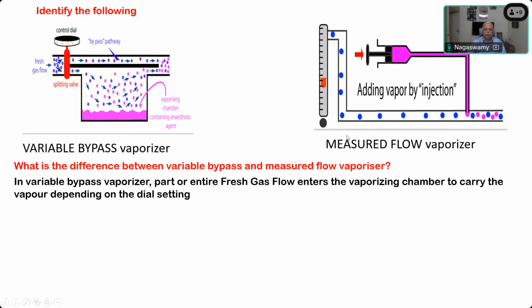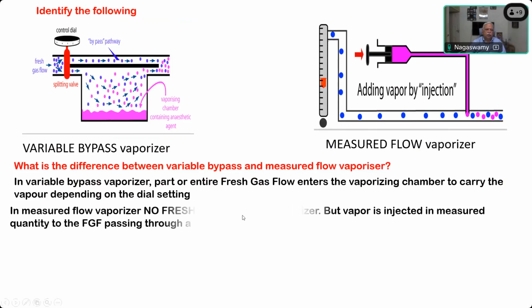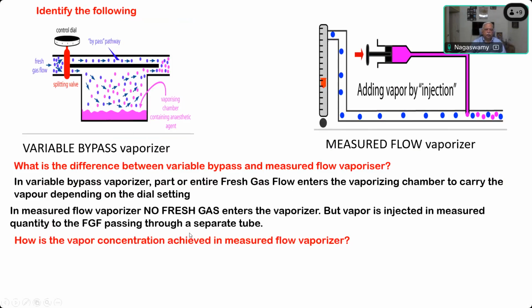Whereas if you see in the measured flow, the blue dot is the fresh gas flow, and this fresh gas flow never enters this portion, the vaporizing chamber. On the contrary, this vapor is allowed to come and join this fresh gas flow as a separate line. So in the measured flow vaporizer, no fresh gas enters the vaporizing chamber, but vapor is injected in measured quantity to the fresh gas passing through a separate tube. That is a major difference. How is the vapor concentration achieved in measured flow vaporizer?